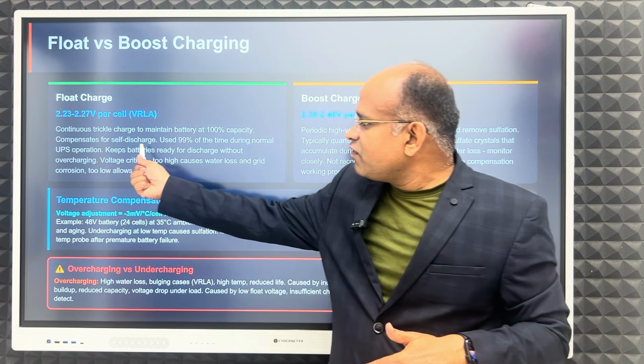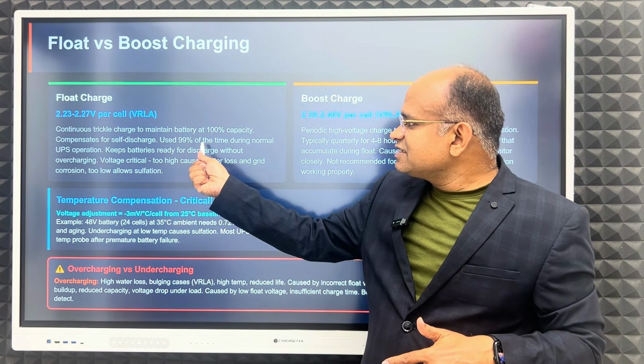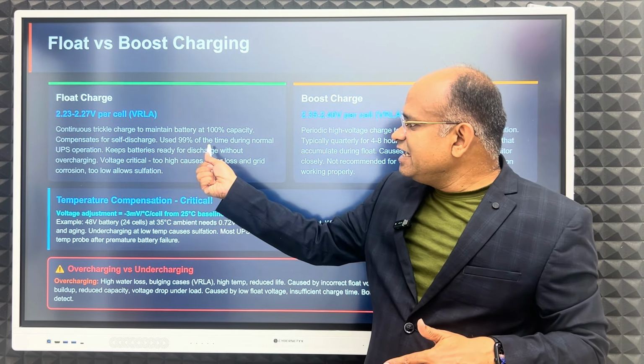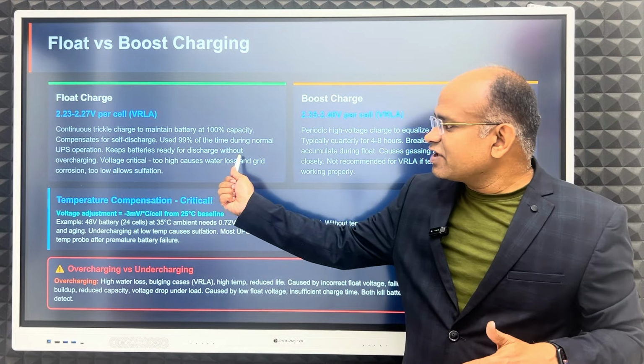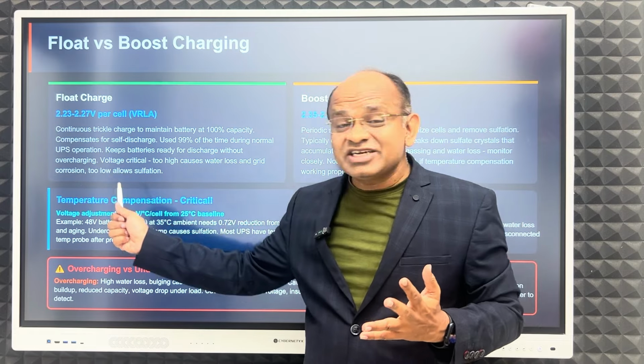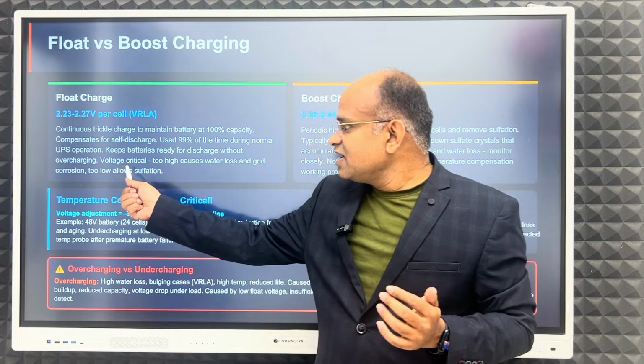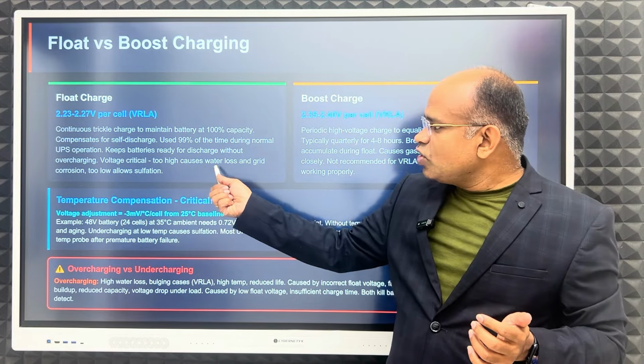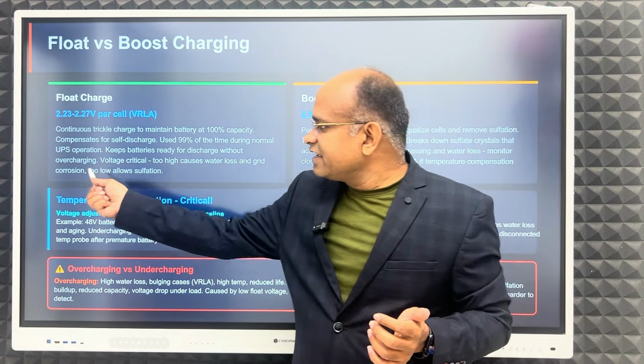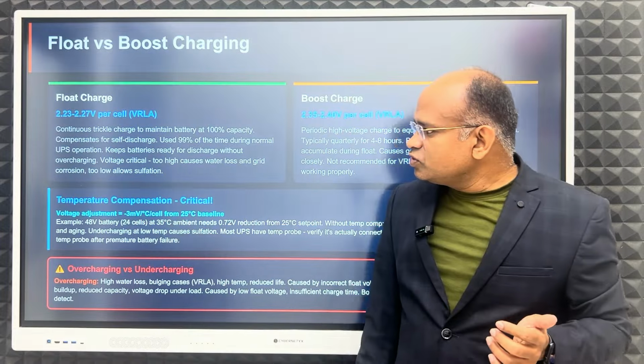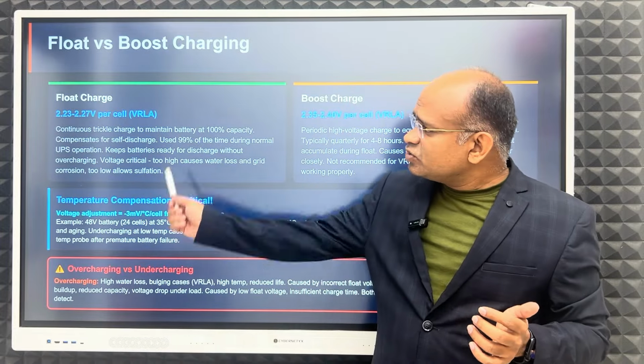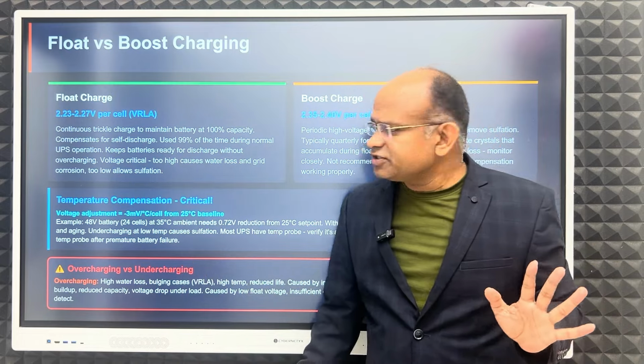It compensates for self discharge, is used 99% of the time during normal UPS operation, and keeps batteries ready for discharge without overcharging. Voltage is critical: too high causes water loss and grid corrosion, too low allows sulfation. So this is the float charge.